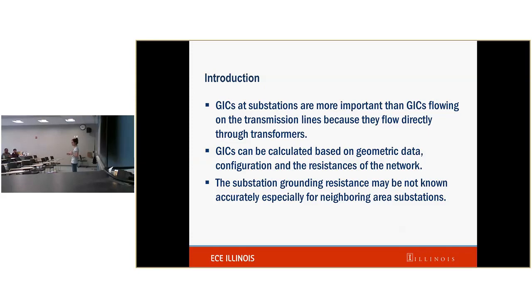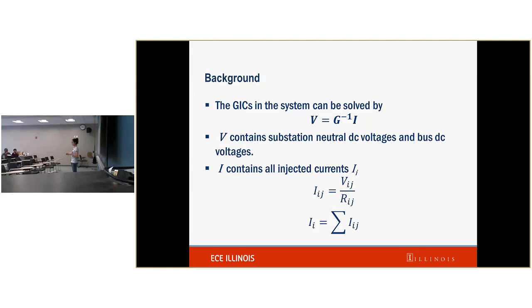Although other resistances, like resistance of transformer and transmission line, are usually included in the power flow model, substation grounding resistance is not readily available. The value used in study is usually just an estimated value, and that can make our calculated GIC imprecise. That's why I study the sensitivity of the GIC to the substation grounding resistance.